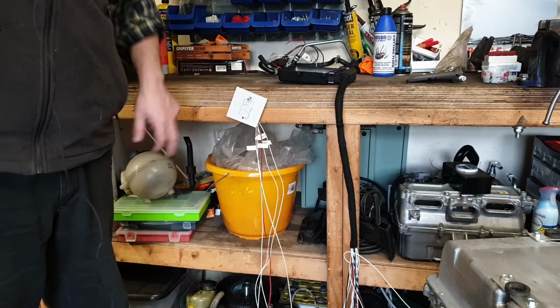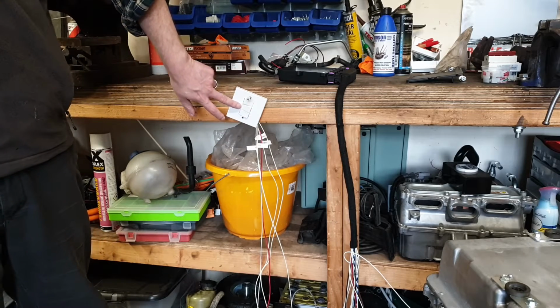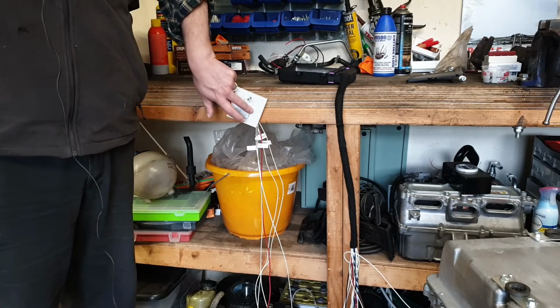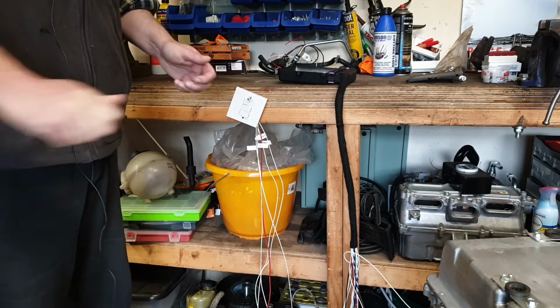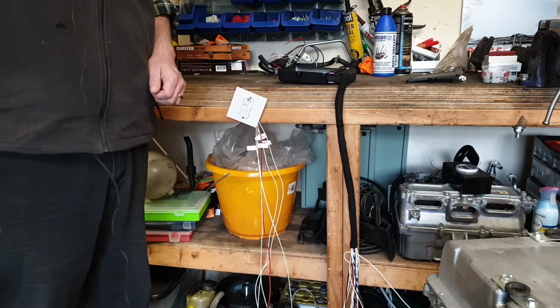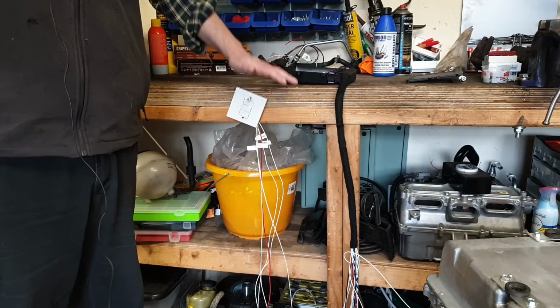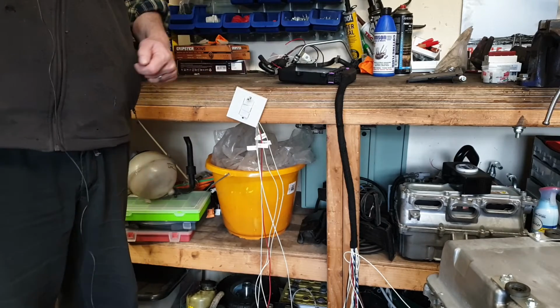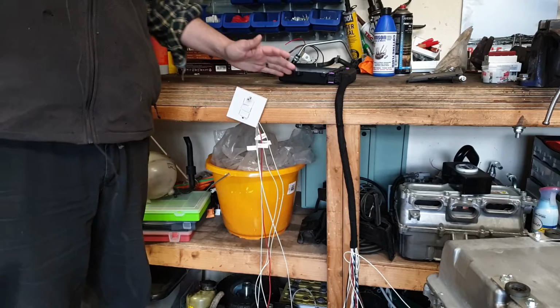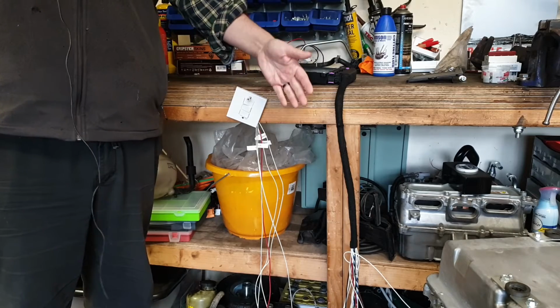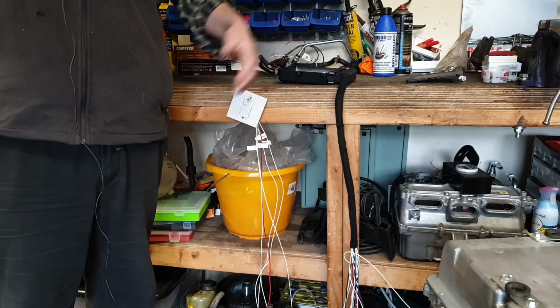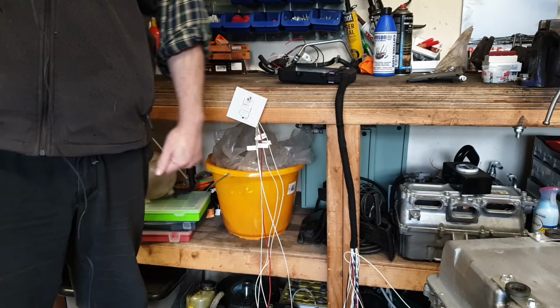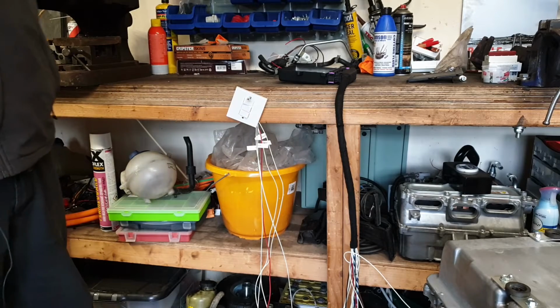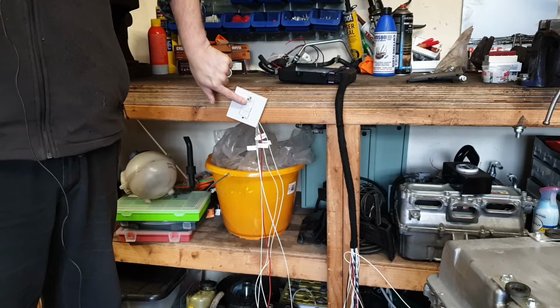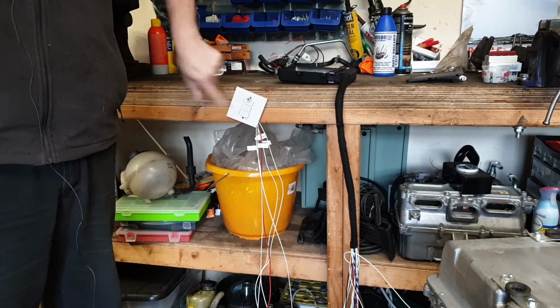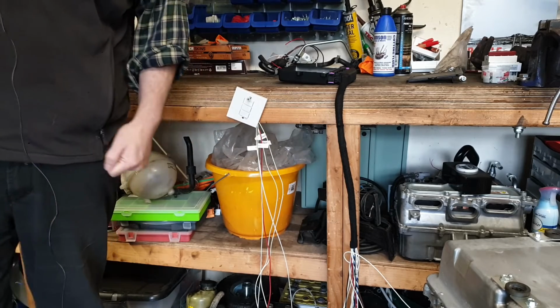And finally, our second little switch here - normally what I do with this is just give it a flick, which would be akin to flicking a start momentary terminal. At that point, assuming conditions are met, the VCU will initiate pre-charge. If pre-charge is successful, we'll close the main contactor, turn on our inverter relay, and we're ready to go for a drive. Then when we come back home, switch off, turn our key off, and the system shuts down.